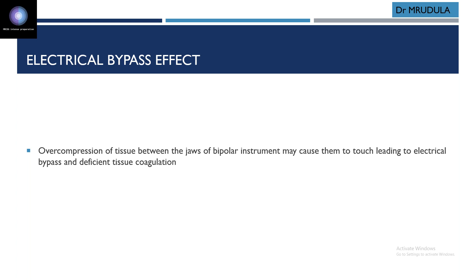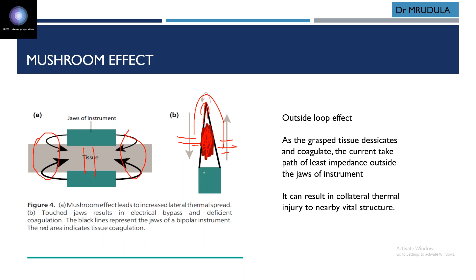So here, touched jaws result in electrical bypass and deficient coagulation. The black line represents the jaws of the bipolar instrument. This bypass effect is because of over-compression of tissue between the jaws of the bipolar instrument. It may cause them to touch, leading to electrical bypass. So because of these instruments touching, the electricity just goes from here to here without affecting this area. Okay.